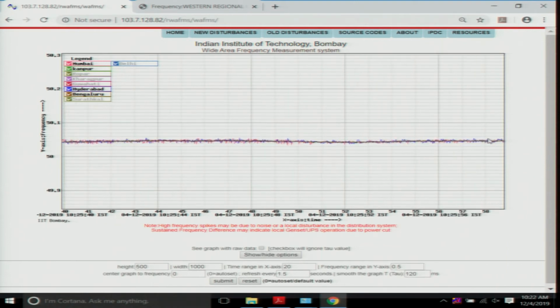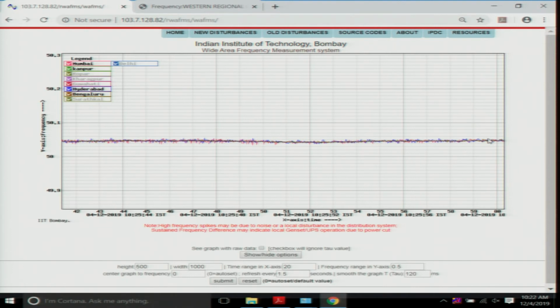The governors in the system are trying to regulate it, though maybe not exactly to 50 hertz, because there may be a dead band in the governors which prevents operation for very small variations in the frequency. So, this is an example of a measurement we are taking, and we can see that the system is indeed operating in synchronism. All the frequencies at various locations in the grid are in fact the same.